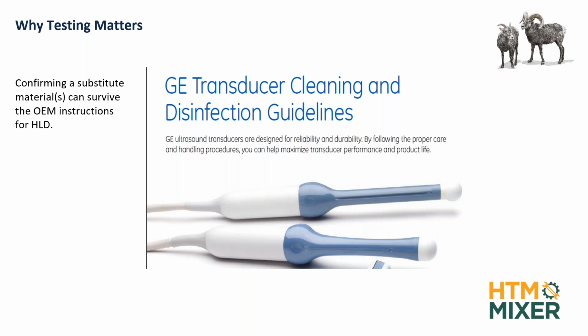So taking things out and not putting them back in, I mean, that doesn't sound like a very good practice. The other thing too is every OEM has certain cleaning and disinfection guidelines for reusable devices. We all know that, right? And they publish that data so that the cleaning personnel within the hospital, or even the sonographer, if they're doing the cleaning, would know what types of high-level disinfecting solutions they can use. They don't tell them what they can't use. They just say, here's what we validate, so you better use these.